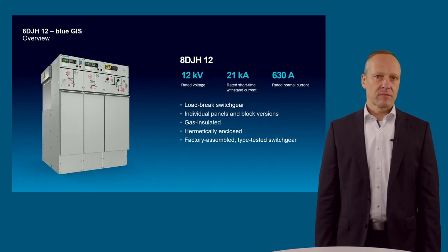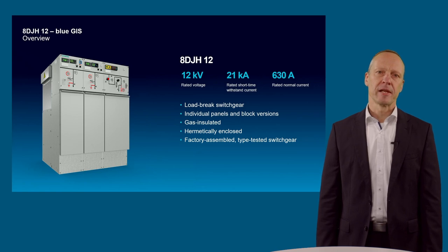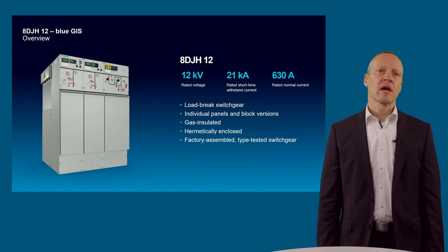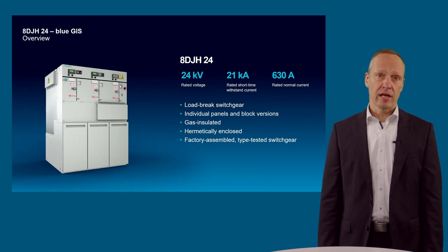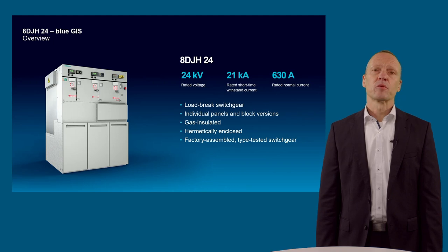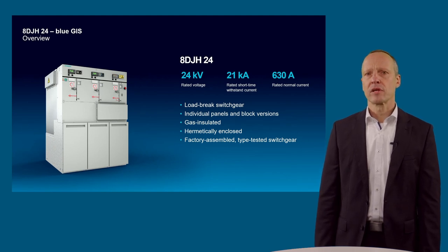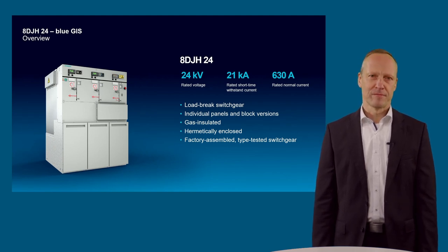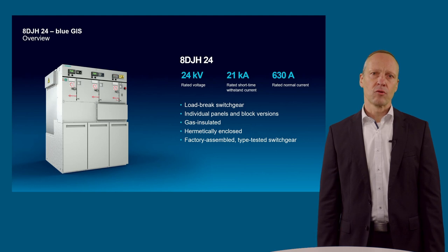Next to the SF6 version, we now have two new Blue GIS members in our 8DJH RMU family: the 8DJH12 Blue GIS up to 12 kV with 21 kA rated short-time withstand current and 630 amp busbar and feeder currents. Both provide three-position load break switches and circuit breakers in different feeder types with well-proven Siemens vacuum interrupters.